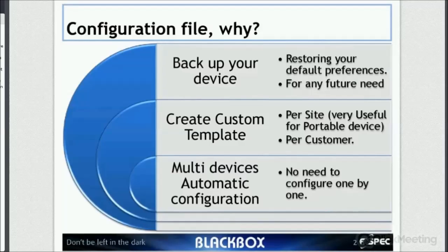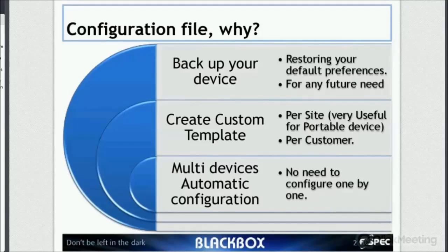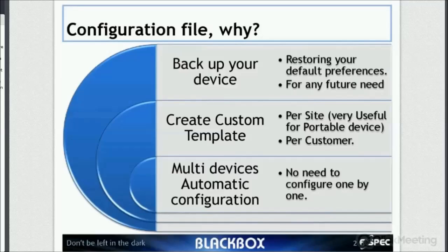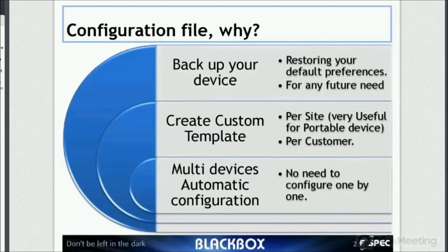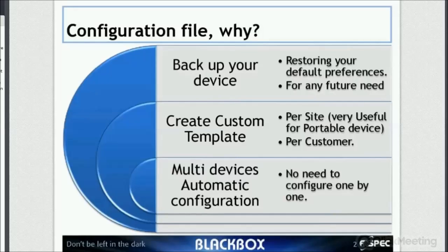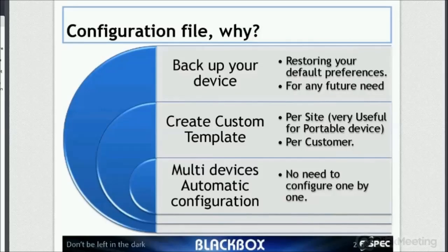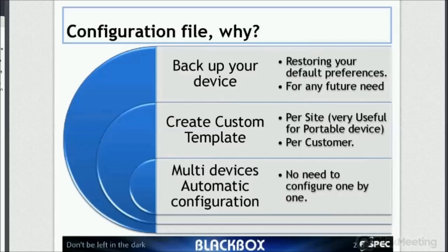Assigning such a configuration file to another device, to use this file as a master file to be assigned to other devices, is not recommended. The reason is that assigning to another device will copy everything, including the calibration, the IP of the device, the name of the device, and some other settings which are not recommended to be copied. Therefore, you would like to copy only specific settings. In order to copy those specific settings, you would use the configuration utility tool. The configuration utility tool is available on the installation CD you have or on the Elspec website.